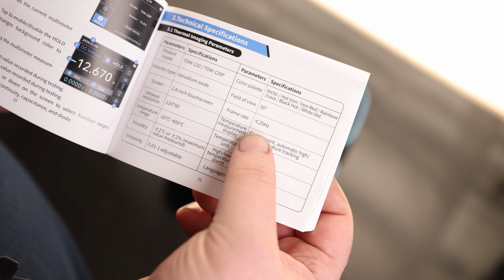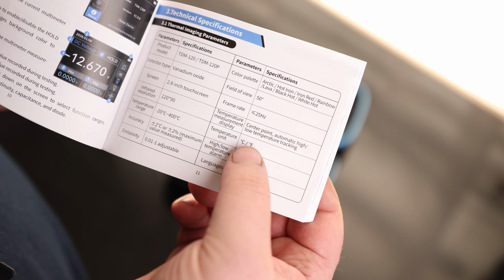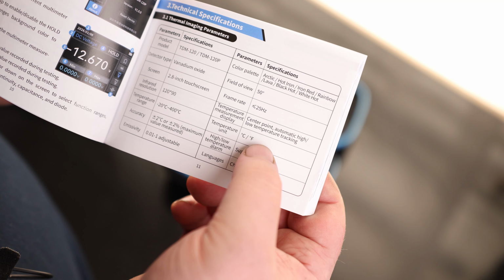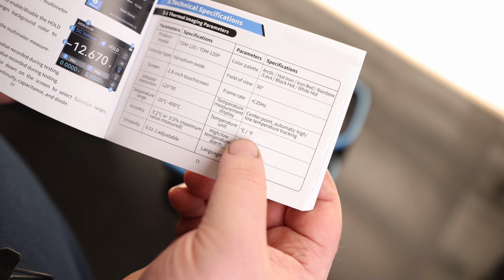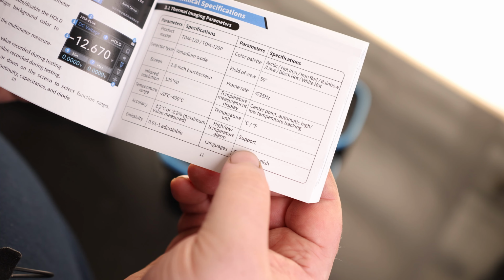We've got a 50-degree field of view, a 25 Hz frame rate. The temperature measurement is center point, with automatic high and low temperature tracking. We have Celsius as well as Fahrenheit, and high-low temperature alarm.